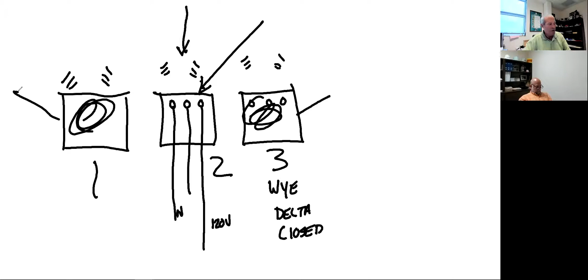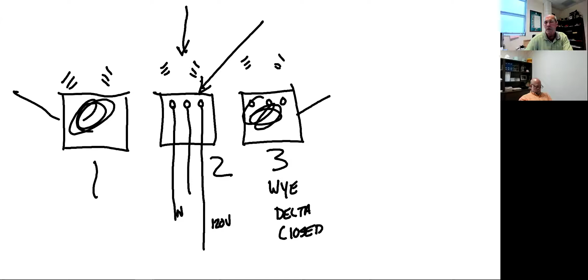Okay, open delta is really easy to indicate. How many transformers does it have? 2. Open delta only has 2 transformers. There's no such thing as a delta or Y 3-phase bank with only 1 transformer - that's single phase, not 3-phase.